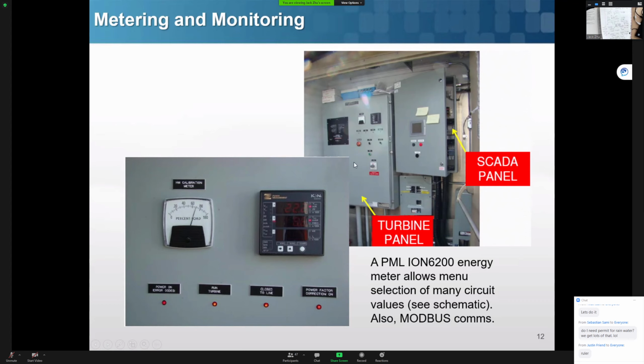The turbine panel is for controlling and monitoring the turbine's moving speed, and because this is a grid connected system, this part has a lot of requirements. BC Hydro requires synchronized protection on there. This is a SCADA panel, which monitors the whole system. This is an HMI display panel. It shows you everything, how this generator is running. We have a picture to show you slightly later.